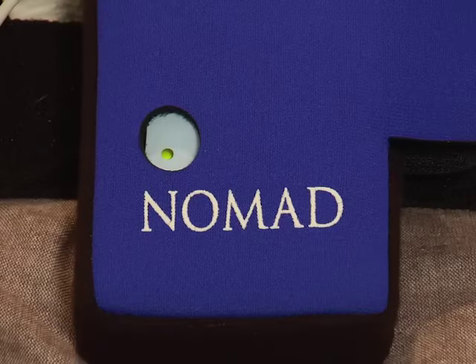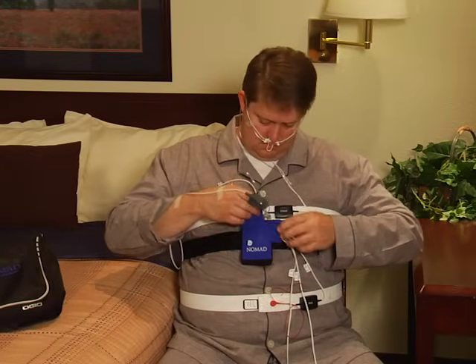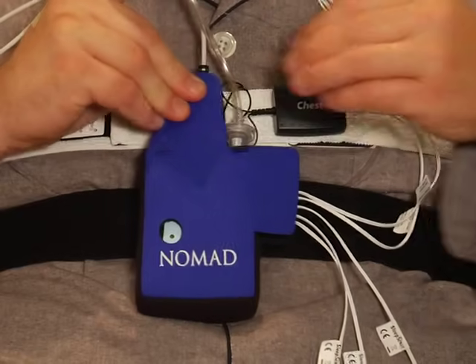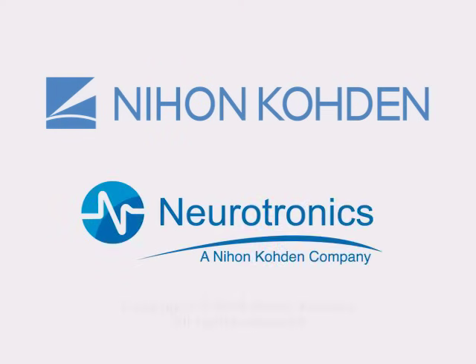About one minute after this last sensor is plugged in, you'll notice a flashing green light that is visible through the front of the pouch. This means that the Nomad has successfully begun recording. If you see a red or orange light instead, please contact your service provider. Before closing the Velcro flaps, please double-check that all the plugs and snaps are still connected and that your belts are secure. All set? Great! Then just close all the flaps on the pouch and make yourself comfortable in bed. Nihon Kohden wishes you a very good night.